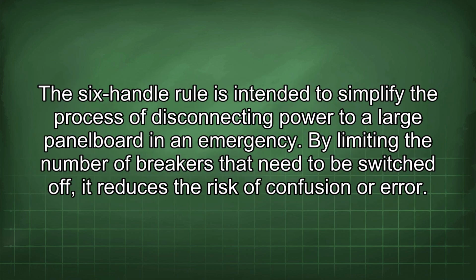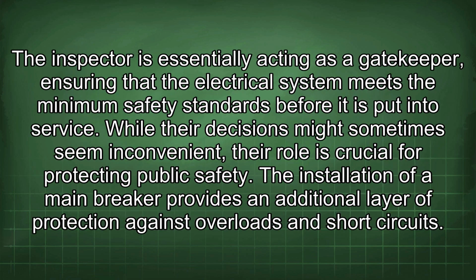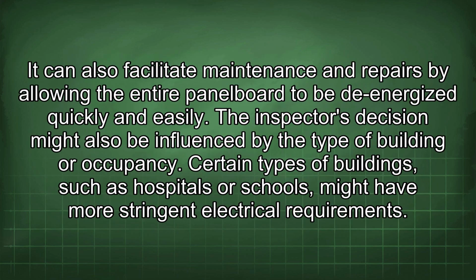The six-handle rule is intended to simplify the process of disconnecting power to a large panel board in an emergency. By limiting the number of breakers that need to be switched off, it reduces the risk of confusion or error. The inspector is essentially acting as a gatekeeper, ensuring that the electrical system meets the minimum safety standards before it is put into service. While their decisions might sometimes seem inconvenient, their role is crucial for protecting public safety. The installation of a main breaker provides an additional layer of protection against overloads and short circuits. It can also facilitate maintenance and repairs by allowing the entire panel board to be de-energized quickly and easily.